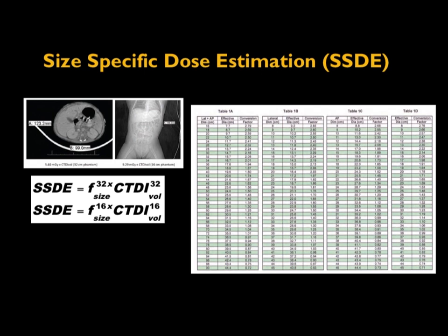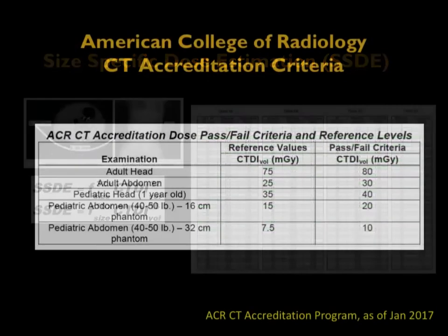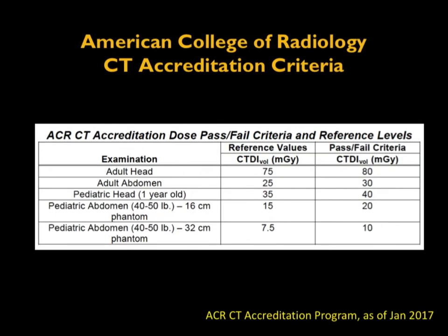The SSDE value is required to calculate organ dose and risk. For sites undergoing ACR accreditation, there are specific dose limits: a site performing pediatric imaging must ensure their pediatric head protocol does not exceed 35 mGy CTDIvol, and a protocol exceeding 40 mGy will result in accreditation failure. The purpose of accreditation is to ensure facilities meet minimum standards and remain within required dose ranges.